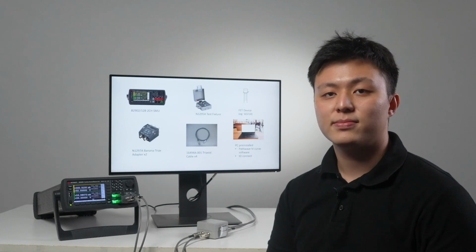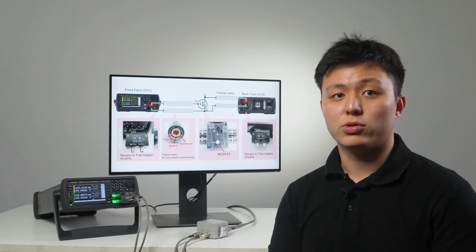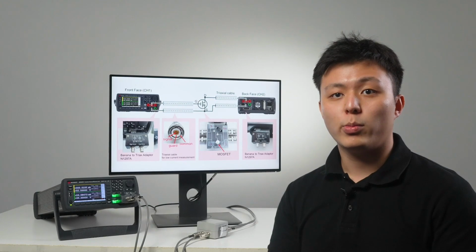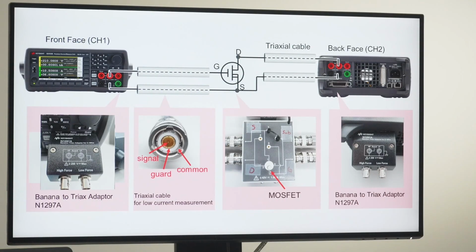ID measurement. First and foremost, to work with source measure unit modules, you will need either the 2902 or 2912 model. These units come equipped with two channels, which is a crucial requirement for measuring field effect transistors. Now, let's take a closer look at the wiring setup.